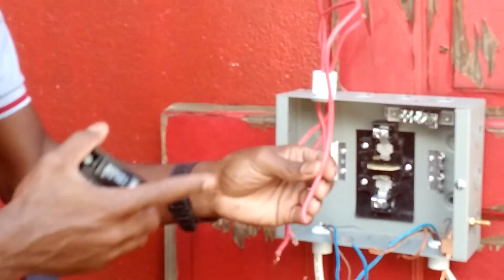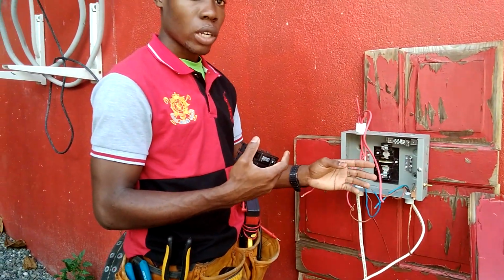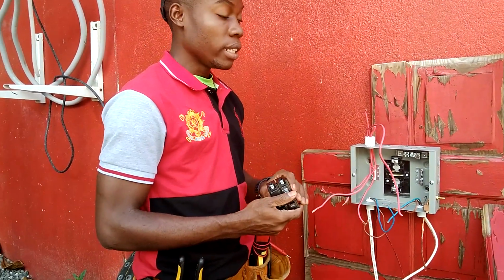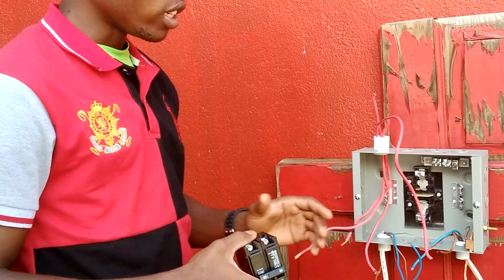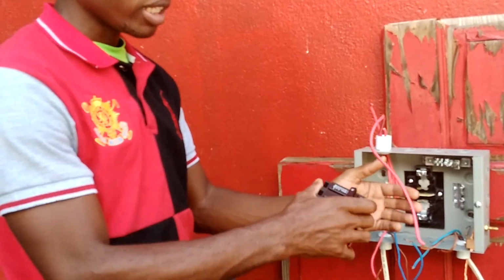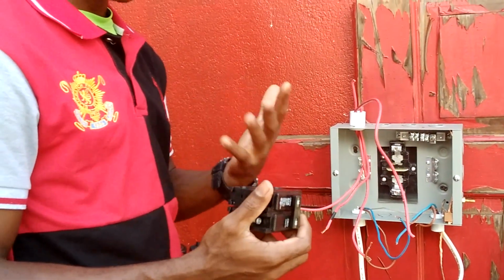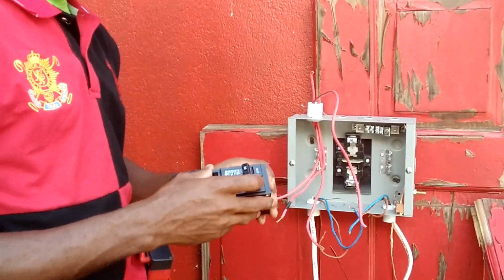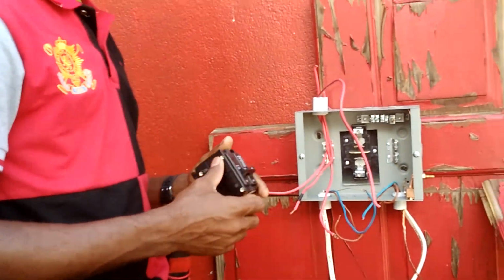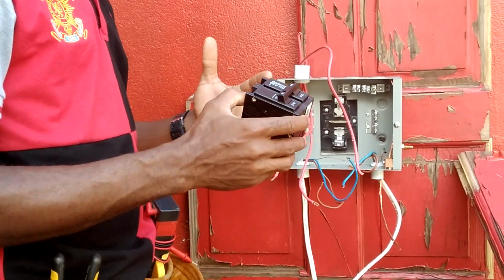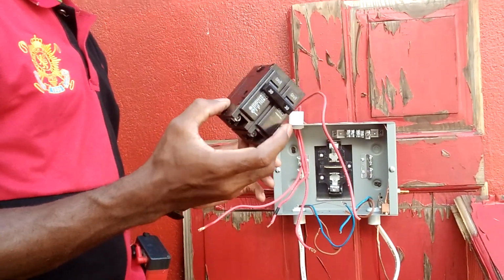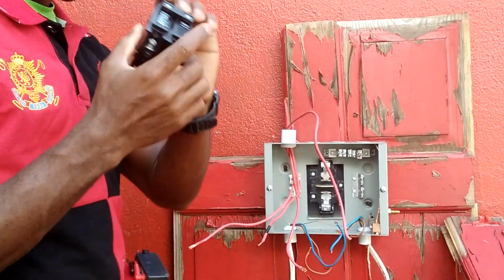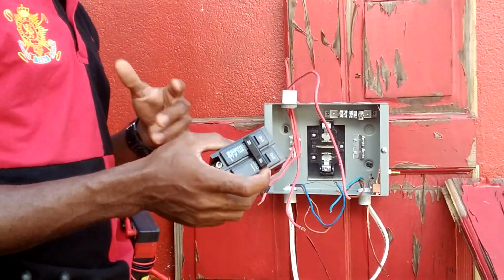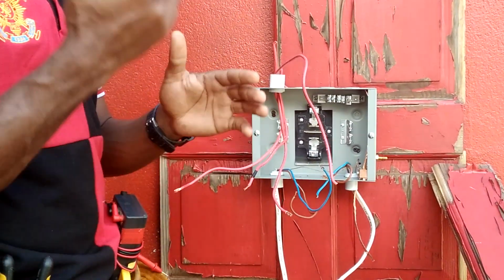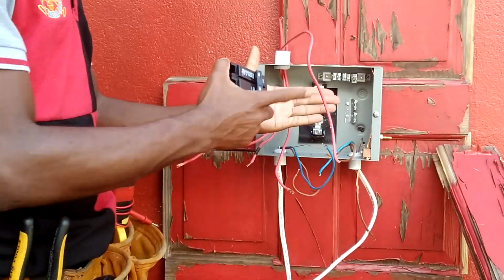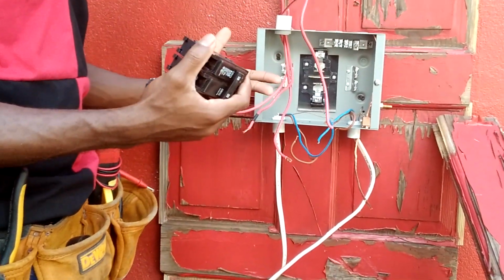The size wire - this is a 6mm square wire. In the JS21, the Jamaican Standard Law, this is a 6mm wire. Now the maximum current this wire can handle is about 40 amps, but for a little circuit like this, we're going to use a 30 amp. You don't want to use lower than 30 amp on this size of wire. You can use 30 or 40 as a main breaker when using this size wire as a main wire.